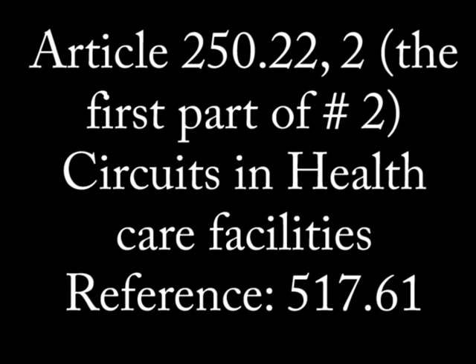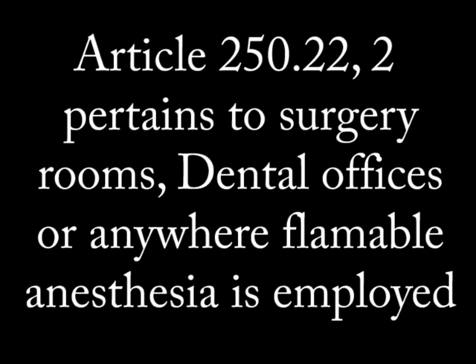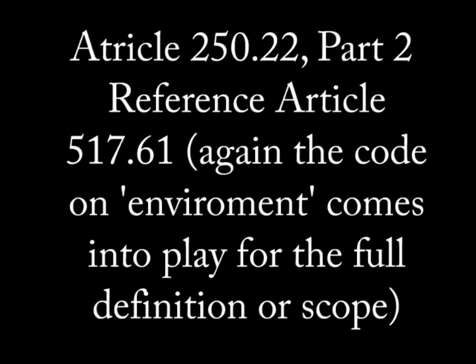Part 2 actually has two items. Systems using anesthesia or other combustible gases shall not be grounded. A good example of this would be a surgical room or a dental office. You can find more details in Article 517.61.